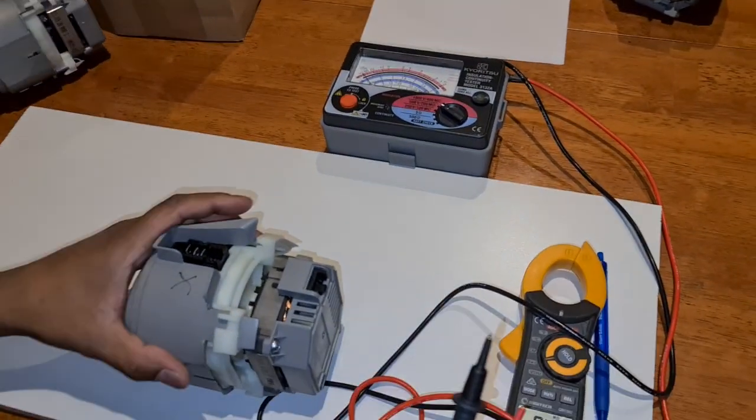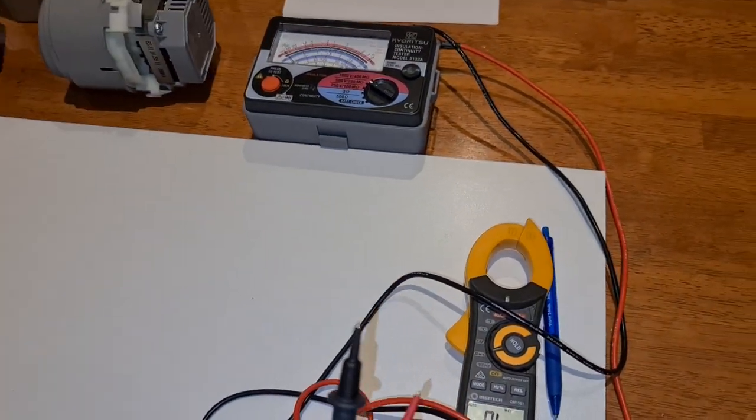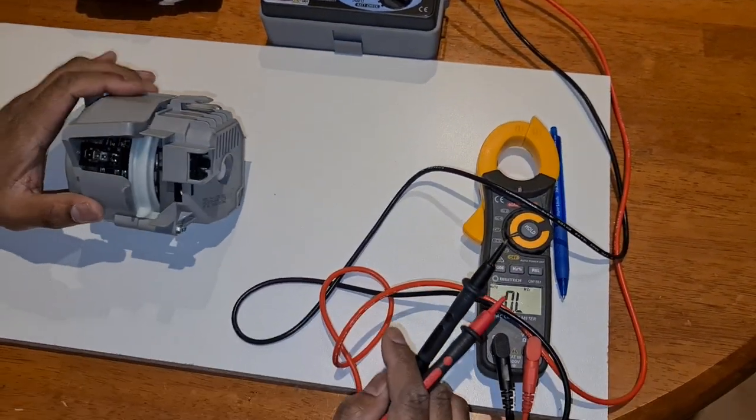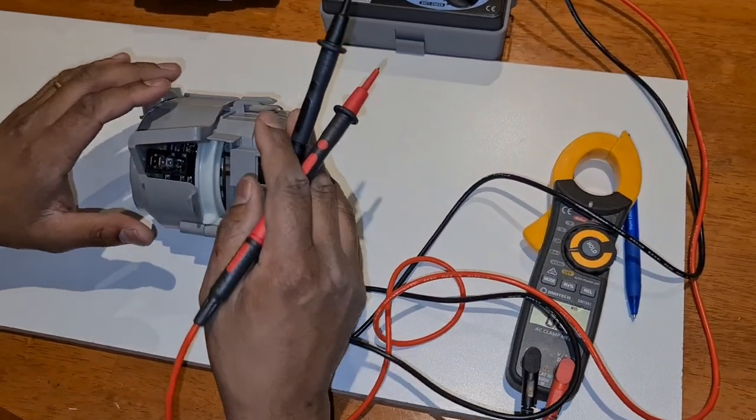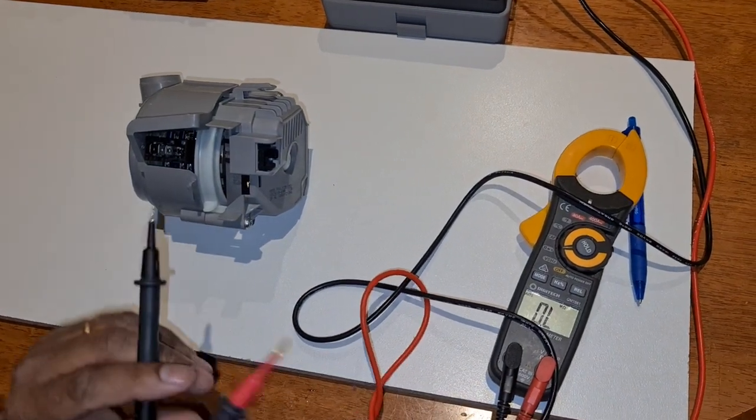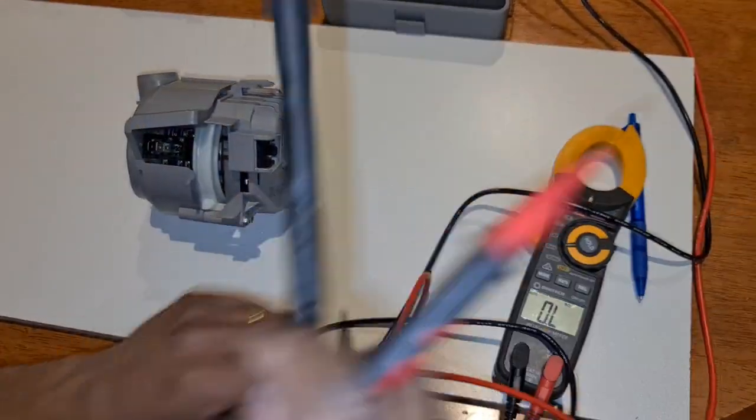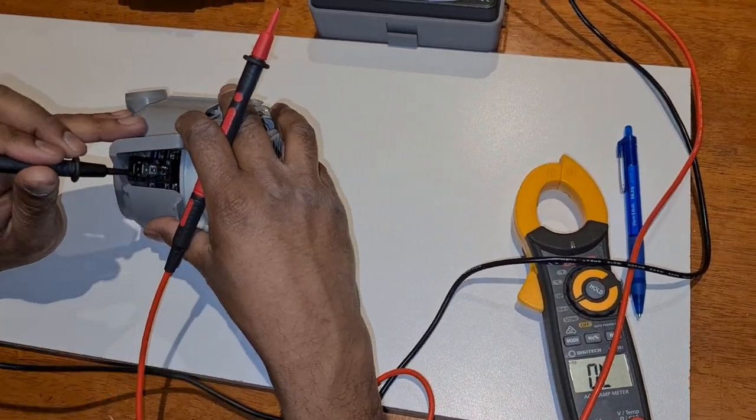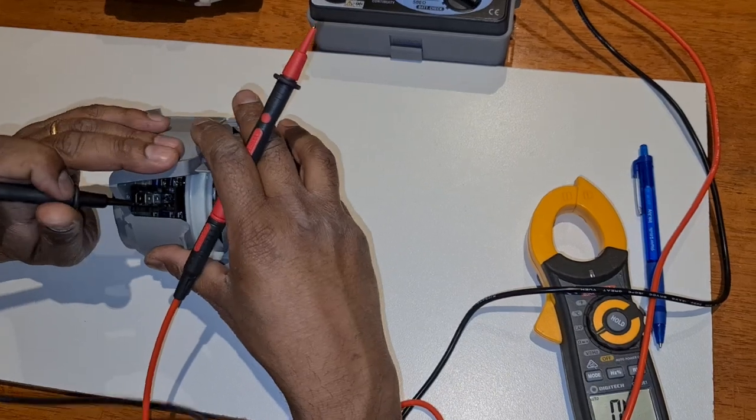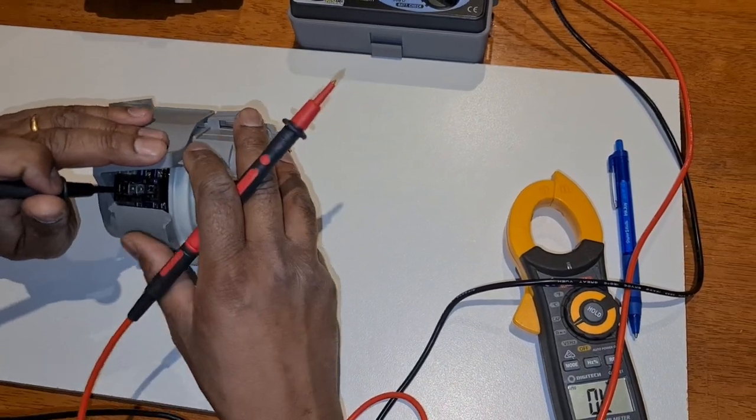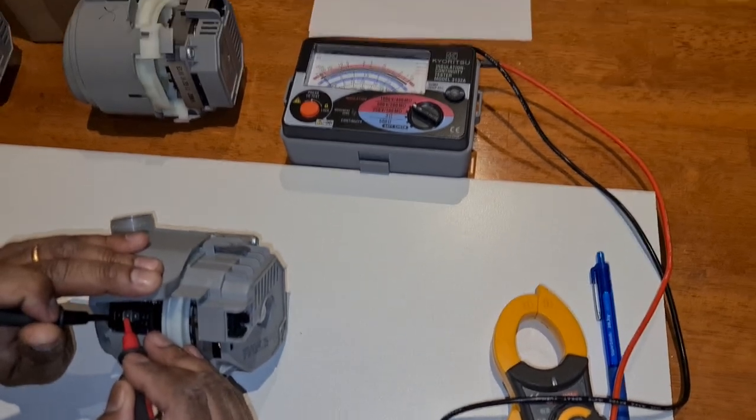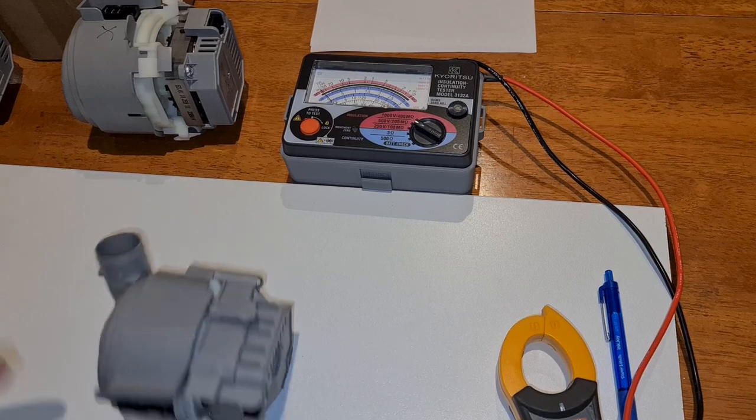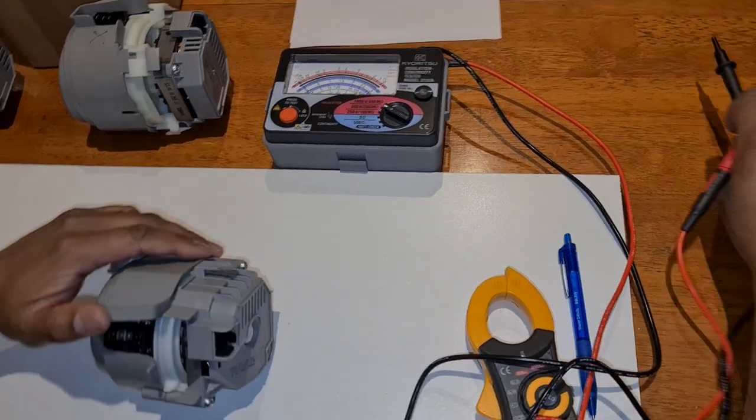So here again, I have another Bosch heat pump. This is slightly smaller in dimensions, but then again, we can use the same principles to test. So let me just... So once again, earth terminal. So our insulation resistance is very good on this pump. But this pump is still bad.